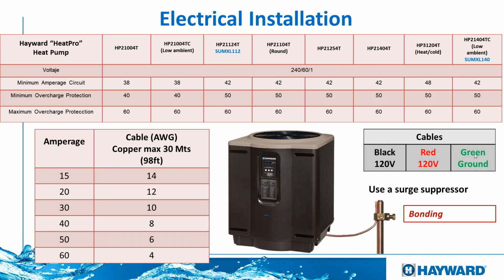Besides the green, it's always very important to put a bonding wire. Don't forget about that. Everything that has electricity, is metal and has contact with water needs to be grounded, needs to be bonded. Two different things. Both of them are very important. So please don't forget that part. And if you want to use some kind of surge suppressor, I also recommend it so we can protect all the boards, all the electrical, especially in all of our countries where we have a problem with voltages. We recommend we put some kind of surge protector big enough for this kind of amperage for a heat pump.